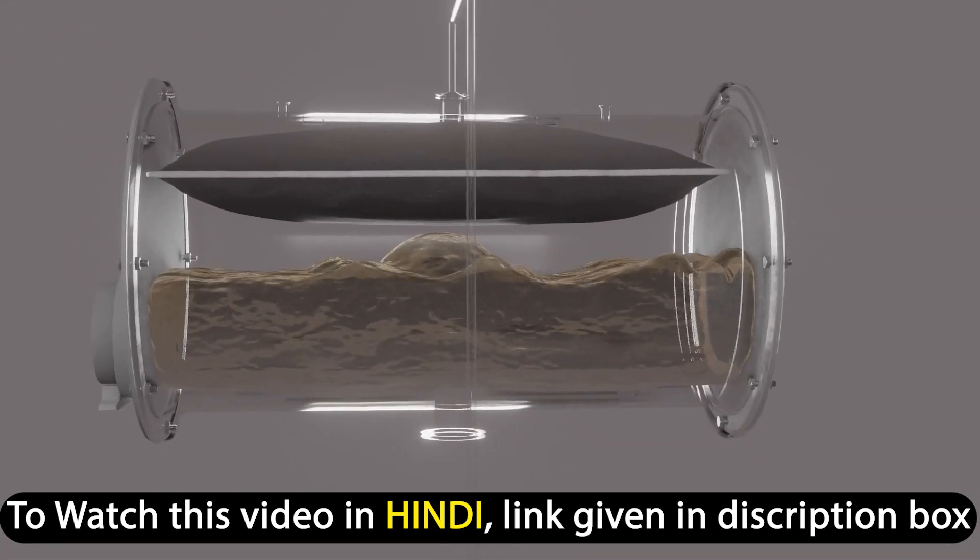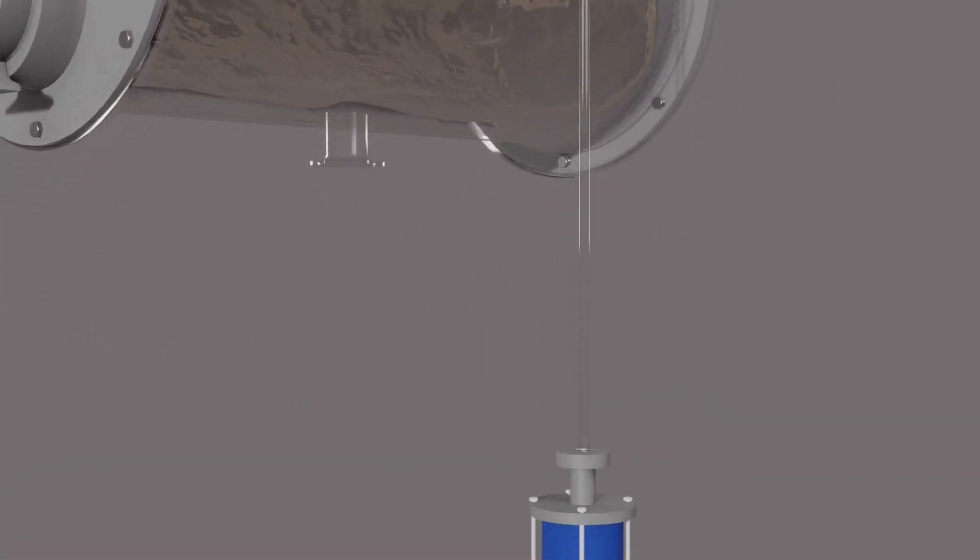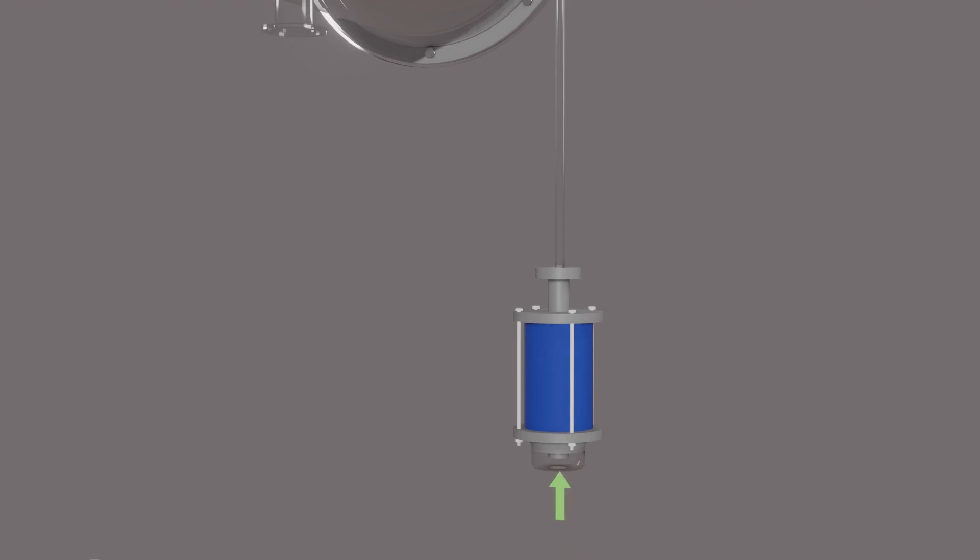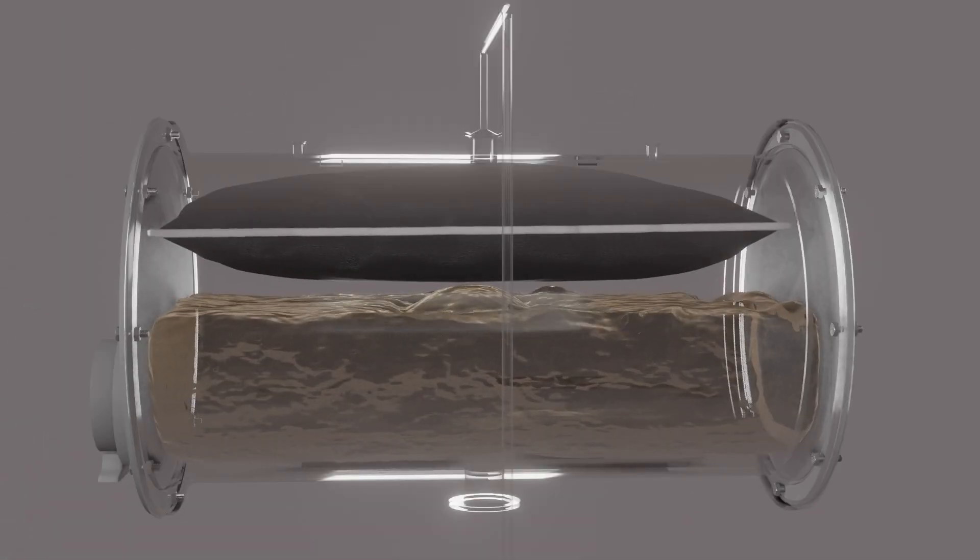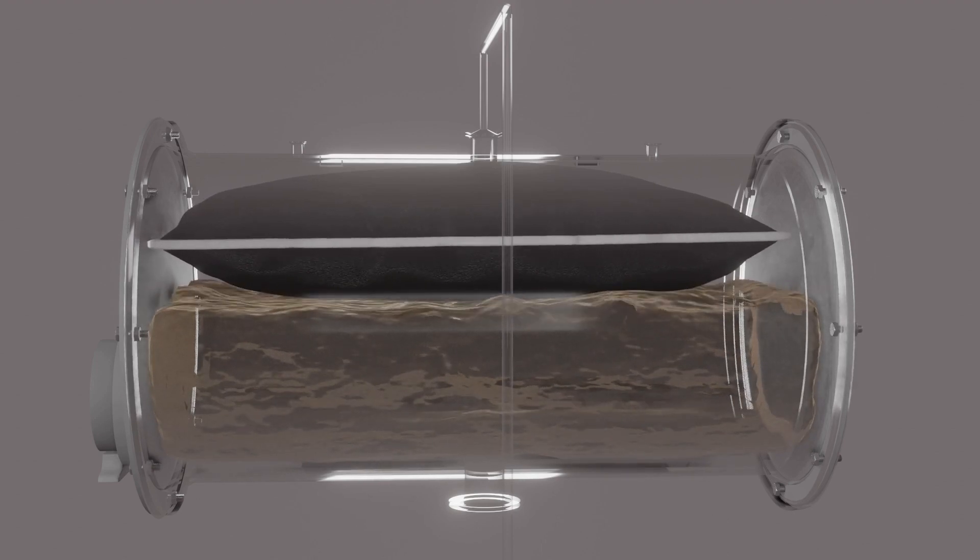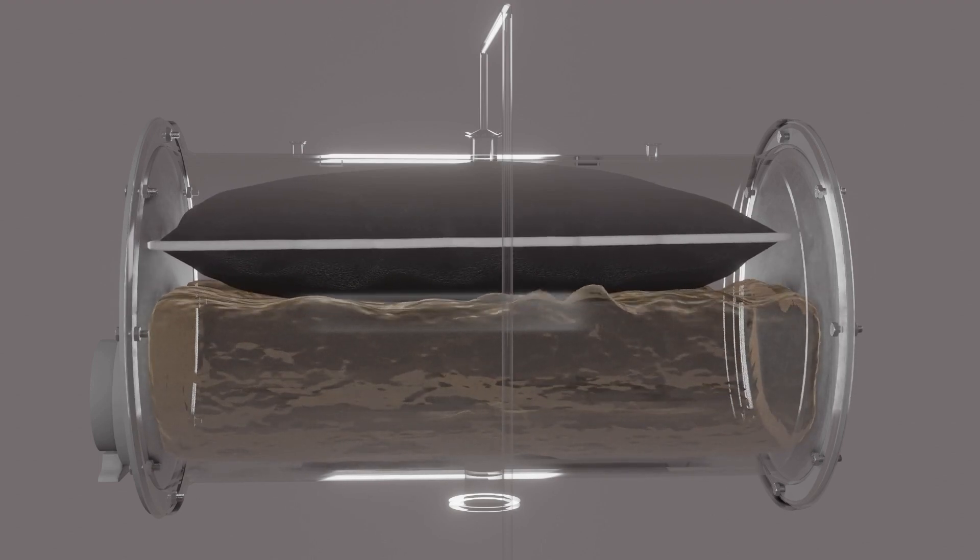Now suppose oil cools down and oil volume reduces. Then atmospheric air comes like this into the air cell and the air cell expands. Now at this time, air cannot come in contact with oil directly, so it will not deteriorate oil or damage the transformer.